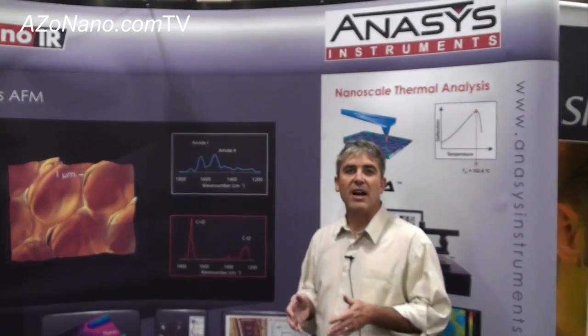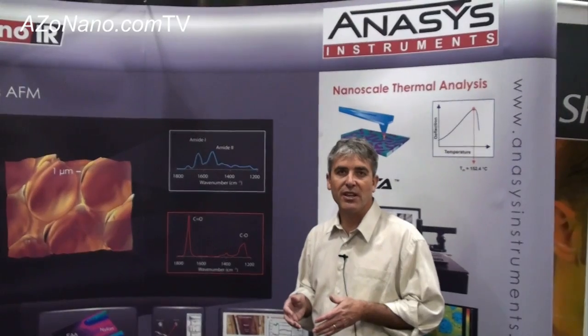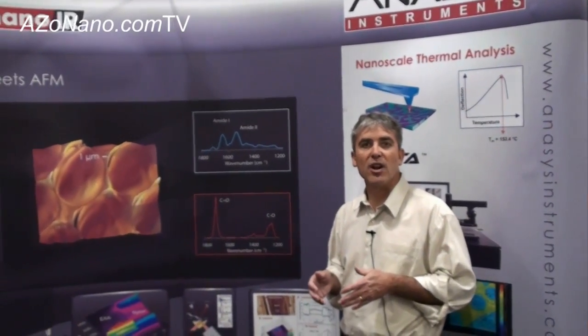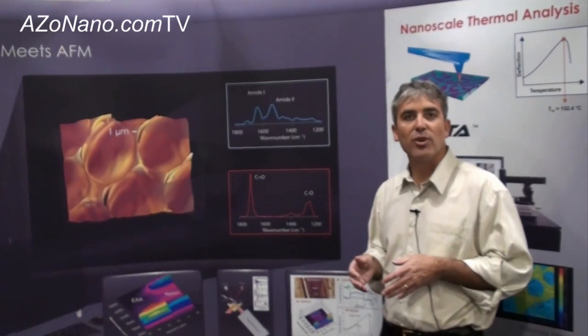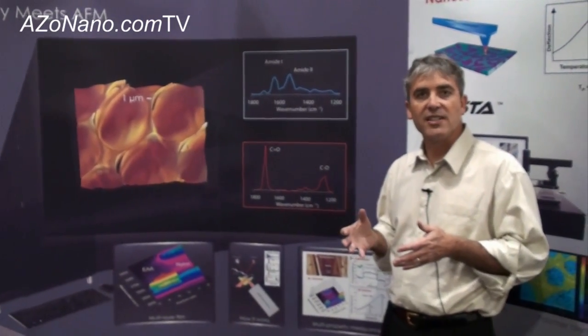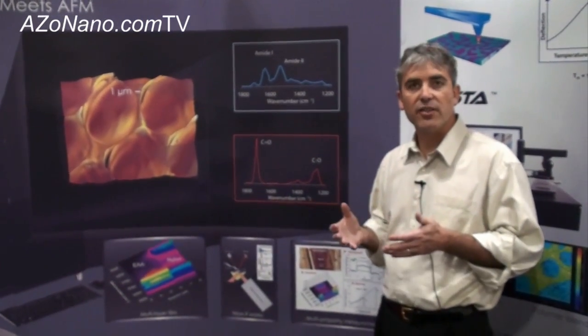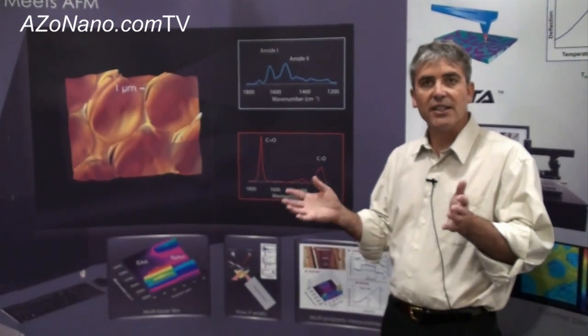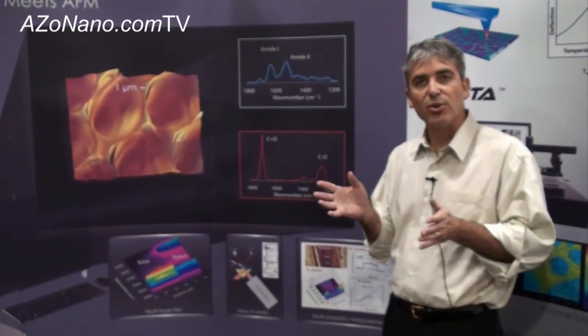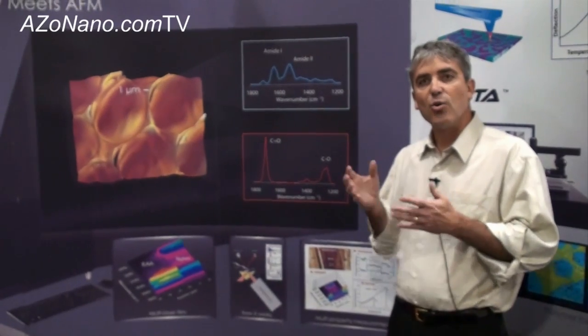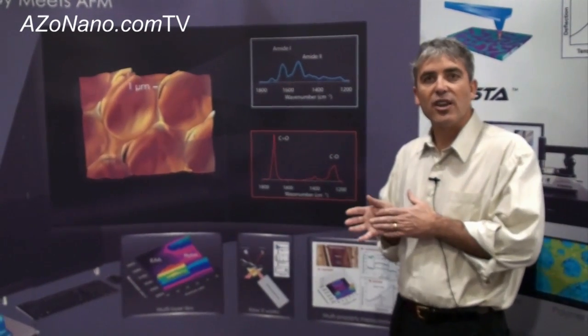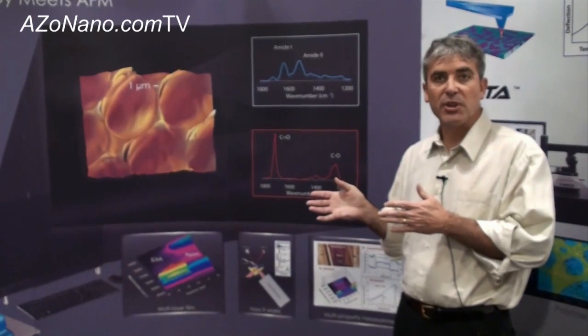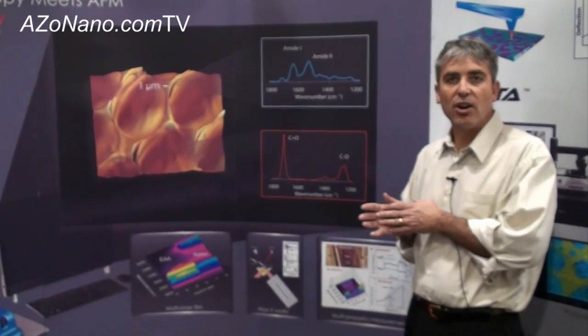What we're doing is we're combining atomic force microscopy with IR spectroscopy in order to give us IR spectroscopy at a significantly better resolution. Current IR spectroscopy is limited by the wavelength of the mid-IR illumination to the diffraction limit, which is typically tens of microns or ten microns. People trying to do nanoscale resolution don't have the resolution within IR microspectroscopy, so we've developed a technique we call nano IR.